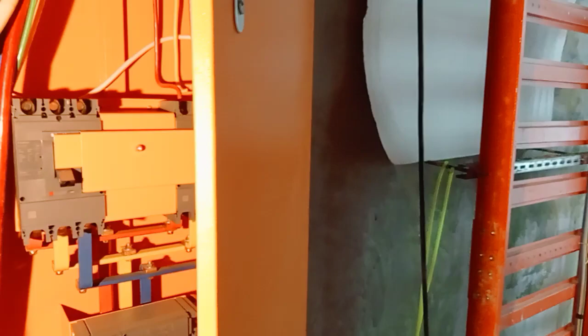So that cable is 250 mm squared in the first cable tray, going to 9th floor. This empty cable tray is for every floor, and we put also cable, 250 mm squared, 4 sets. So every floor there is a panel board.